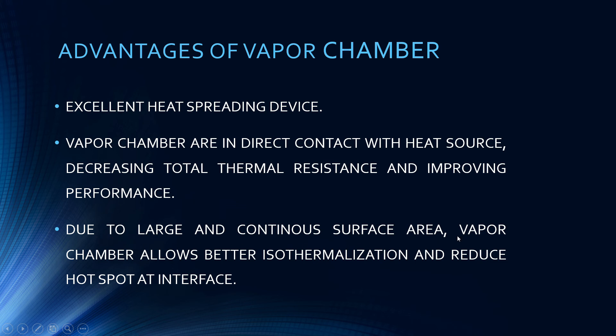The third advantage: due to the large and continuous surface area, the vapor chamber allows better isothermalization and reduces hot spots at the interface. The evaporator area and condenser area are in the same parallel plane and are large, resulting in uniform heat spreading. Hot spots are eliminated at the interface, which increases the lifespan of the vapor chamber and reduces the chance of failure.